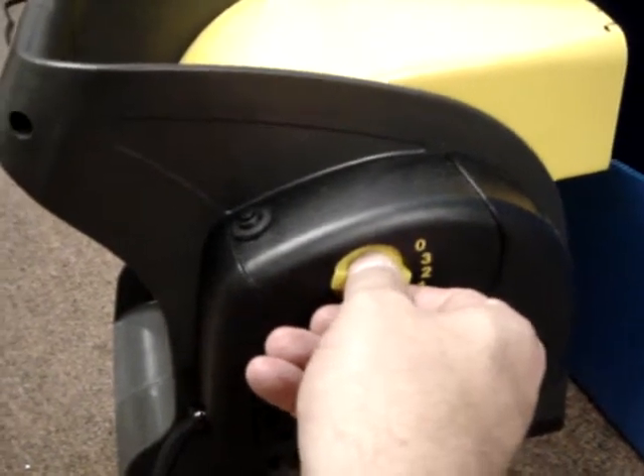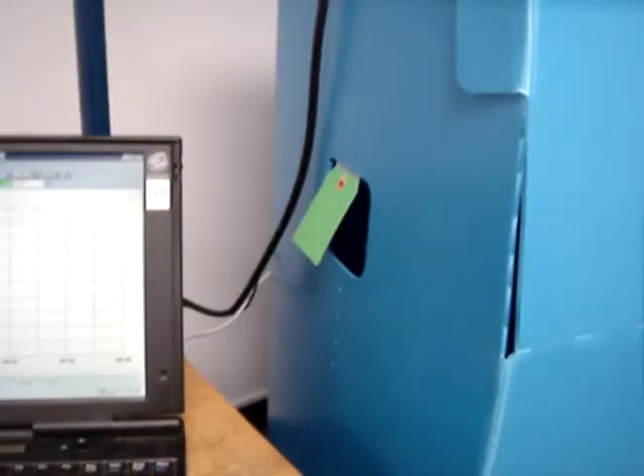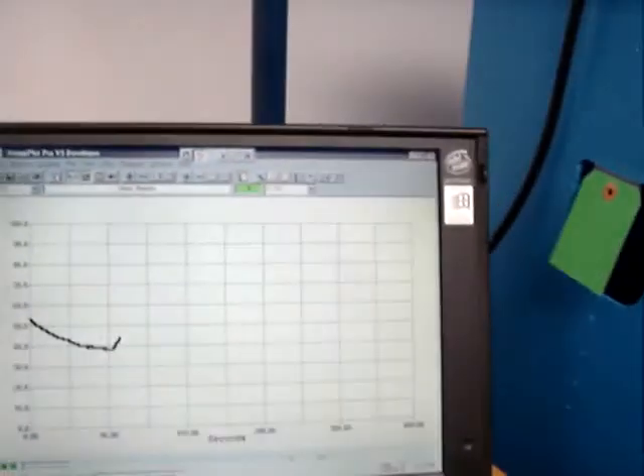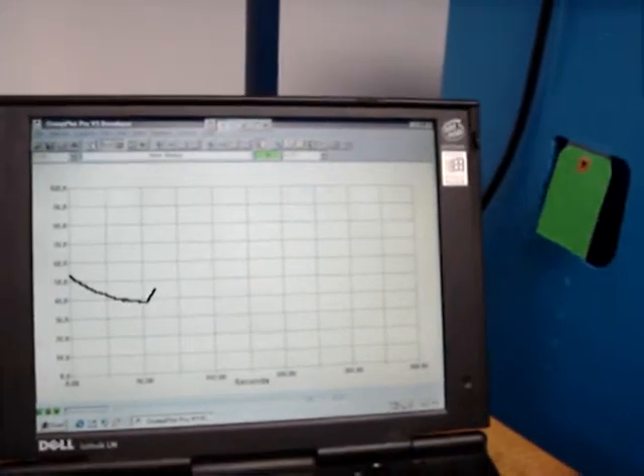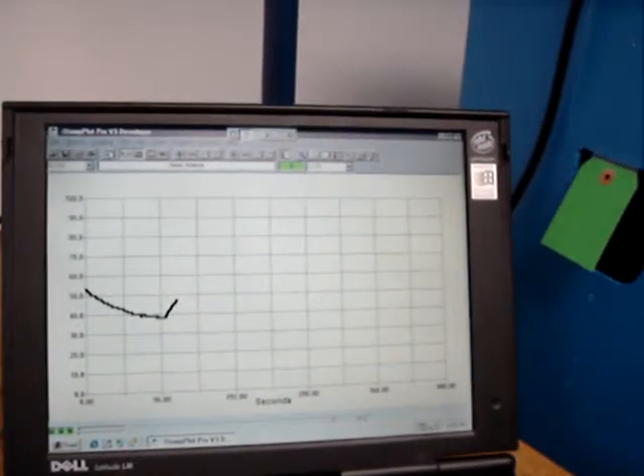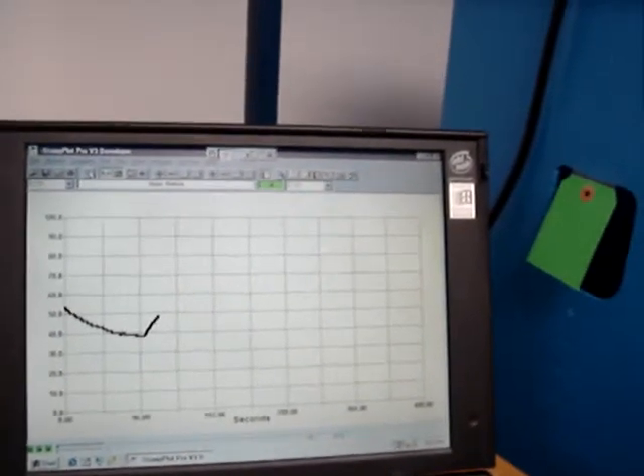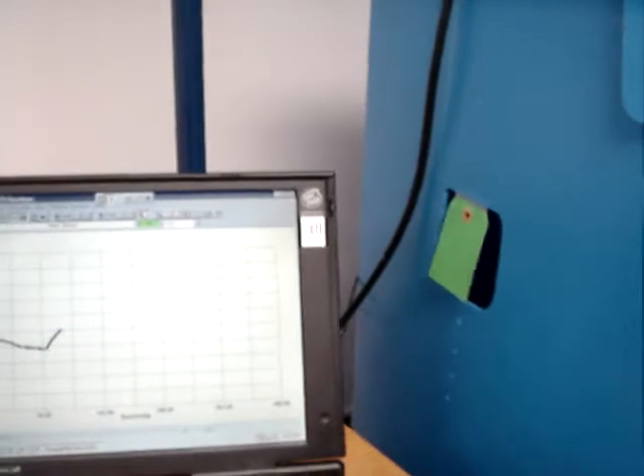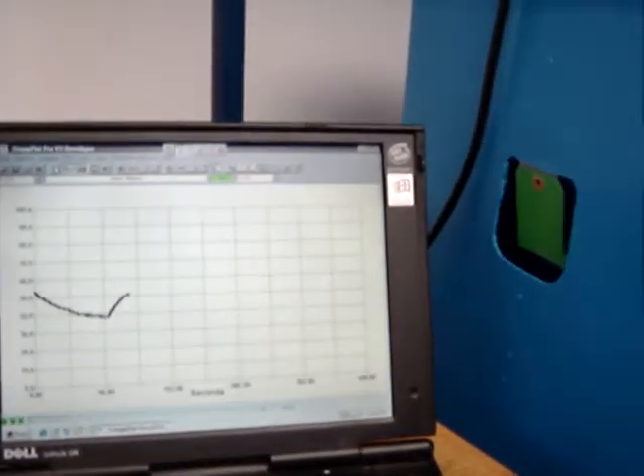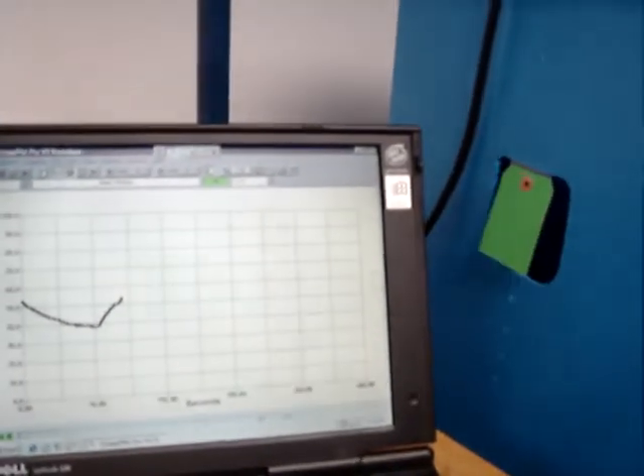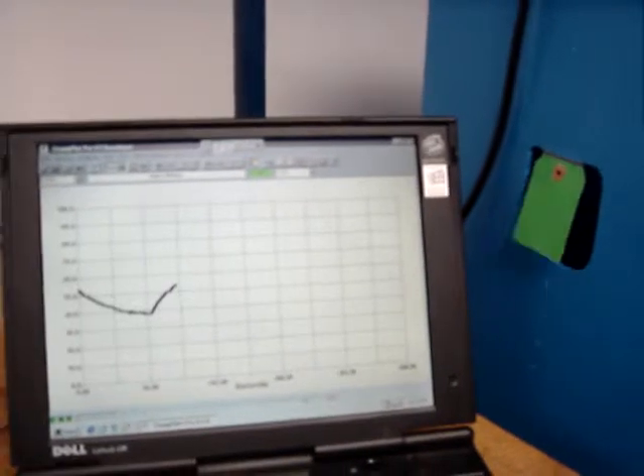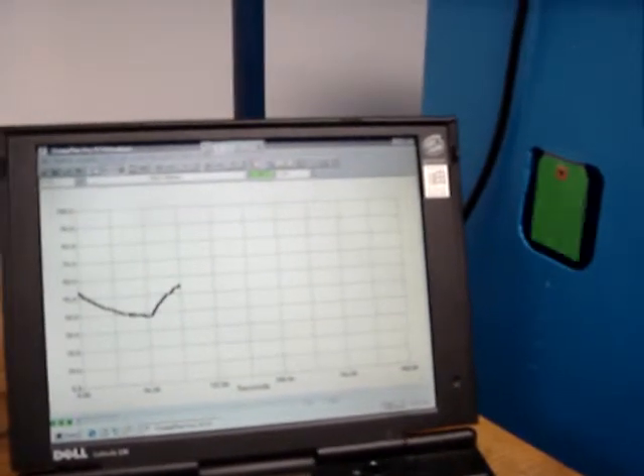So what I'll do now is come over here and turn the fan on high, simulating that the servers are speeding up their fans. You can see that the pressure inside the cabinet is causing the flap to blow out. And you can also see the corresponding increase in the fan speed. And again, the laptop is just plotting the speed of the fan. The laptop isn't controlling the speed of the fan. The speed of the fan is being controlled by the CFM sensor. So again, it'll find the point where the exhaust fan matches the CFM of the server's fans.